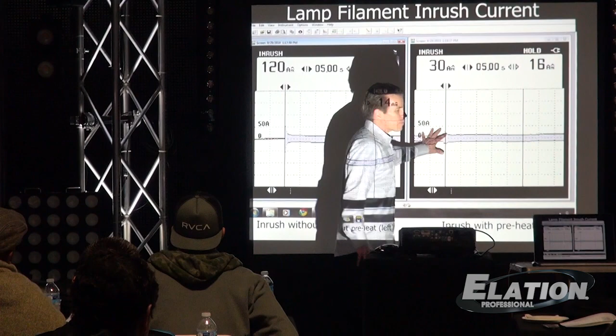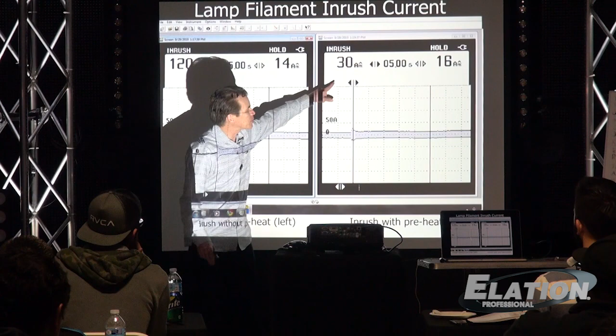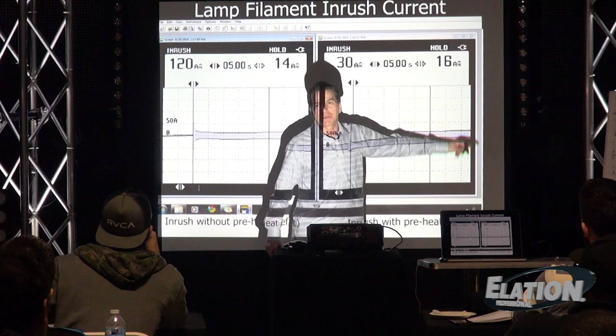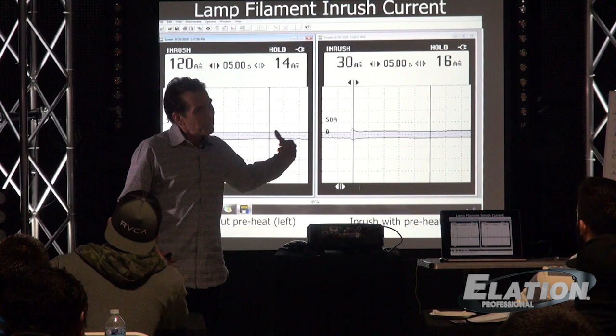Then on the right-hand side, we preheated the filament to 3%. So there's a little bit of current going through the filament, but you can't tell that it's on at all. But then when you turn it on, because the filament's already warm, there's not as high of an inrush. The inrush current was only 30 amps, and then it dropped back down to 16 amps. So you can see that it does have quite a bit of an effect. Now that's for incandescent lamps, which are becoming more and more rare all the time.